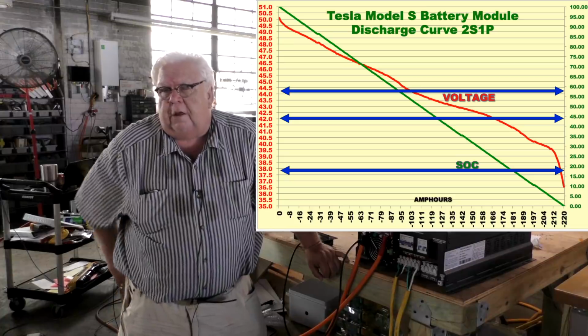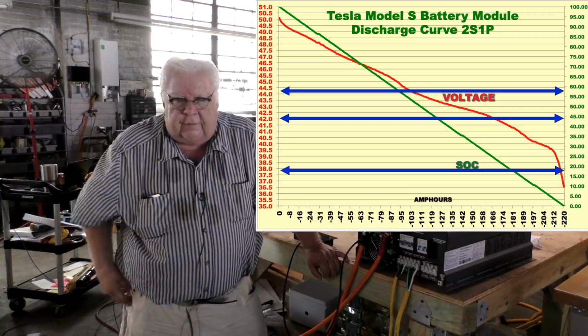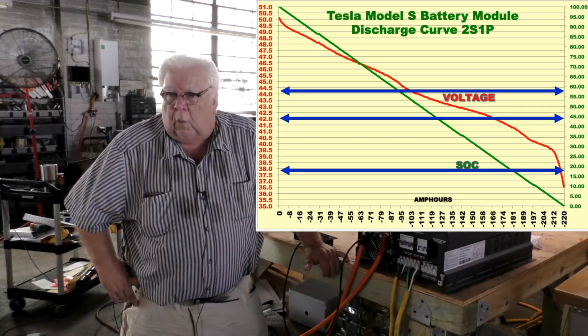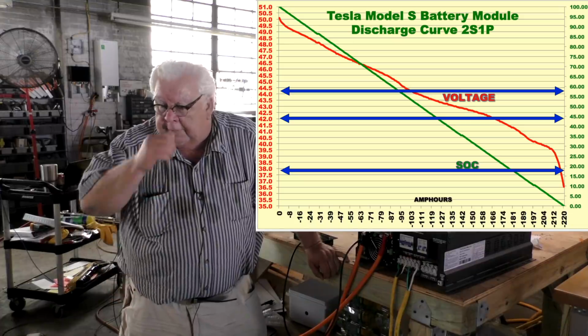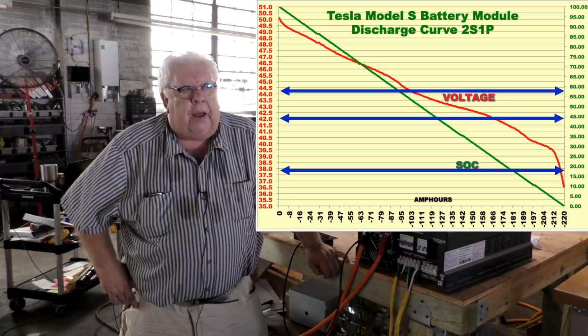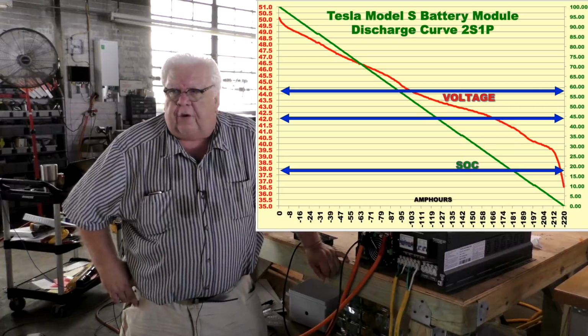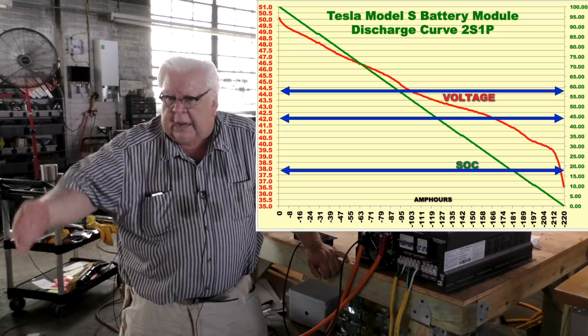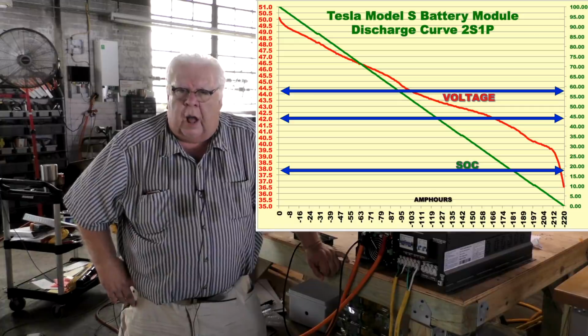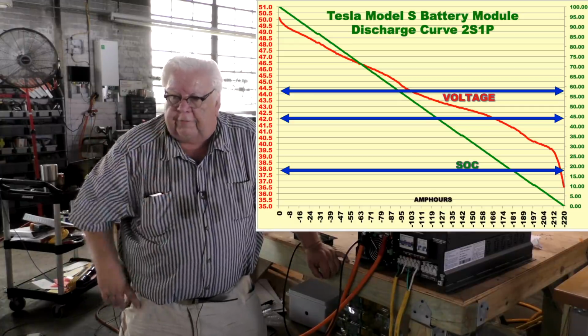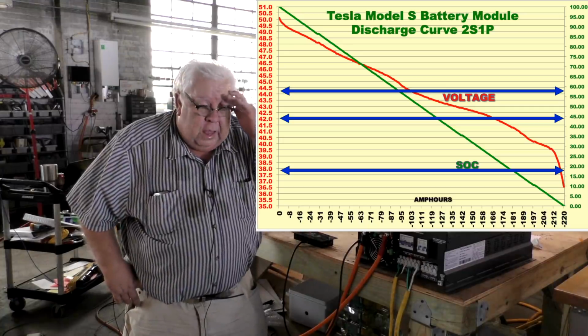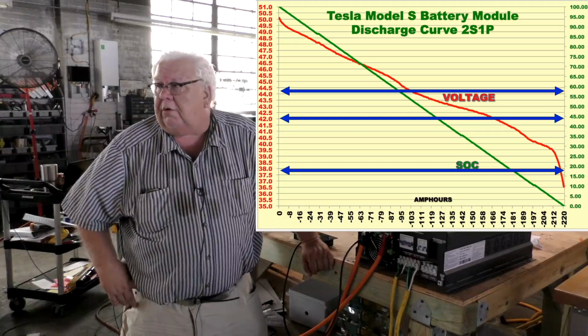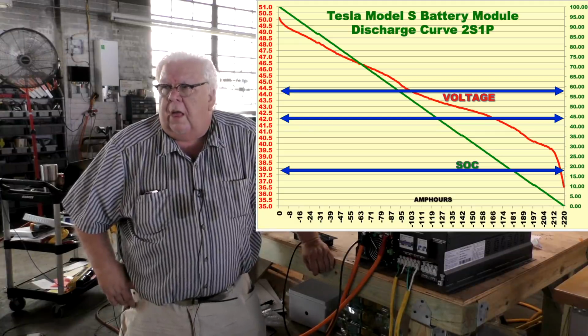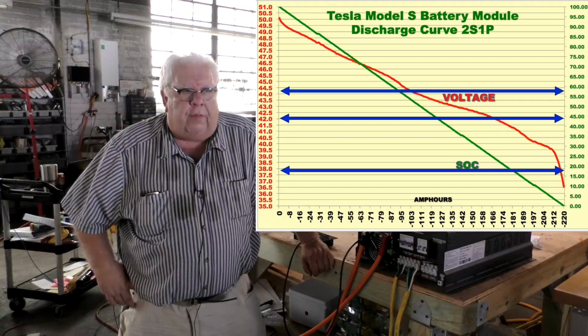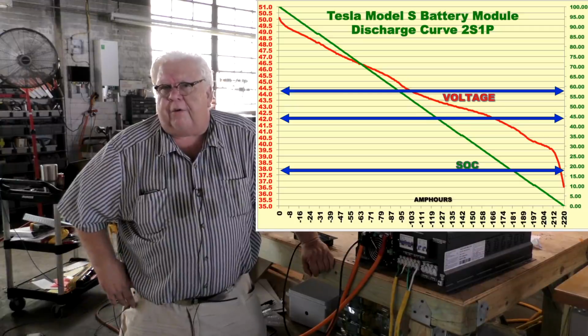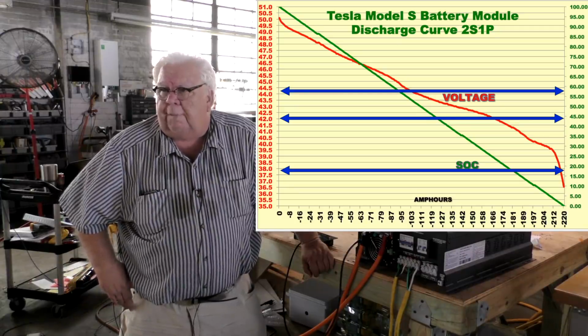In the first place, if you charge these 48 volts, you know, 2 in series, 2 in parallel is 20 kilowatt hours of 48 volts in that Tesla stack. That's great, but they're shot, completely discharged, at about 36 volts, and you're at the serious knee on the curve at about 38 or 39 volts. I'll put up a discharge curve for you to see here. And at 44 volts, my God, you're almost at 60% state of charge. At 42 volts, you're almost at 45%. And so most of this equipment's cutting off and leaving half of your capacity on the table. That doesn't work very well.